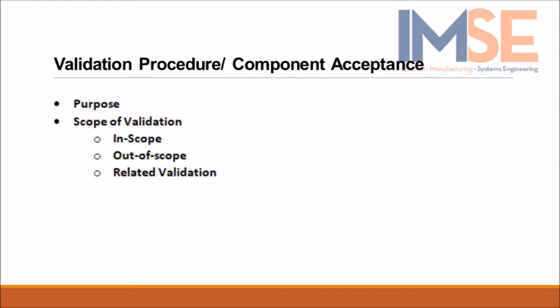Scope of validation. This validation plan for the hood latching system is limited to the unique components and control systems that define the equipment. This validation effort will be conducted as a prospective validation. This section also includes the in and out of scope validations and the related validation. In this situation, the related validation will occur in support of the hood latching system, which includes all procedures necessary for the system to be placed into operation.